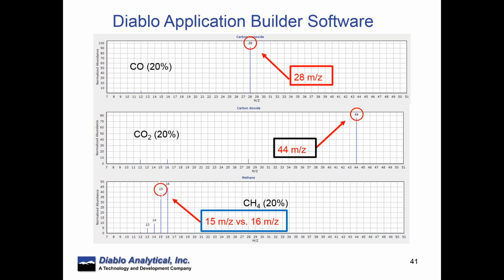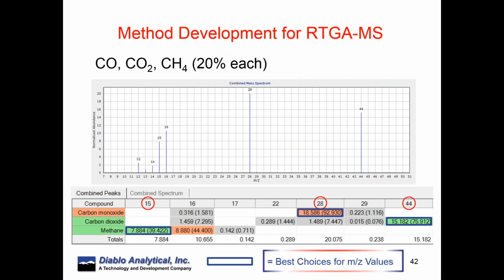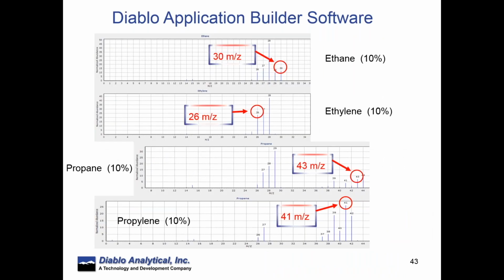Now you can see there is a slight interference between carbon dioxide and CO. So it would depend a little bit on the relative concentration of both of those. And then methane. These would be the best choices for these three gases. If we look at all three of them together, this is what the mass spectrum of the three components at 20% each looks like. And you can see that the detailed numbers in the table show us what the level of overlap will be, if any.